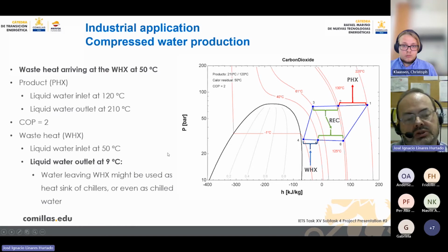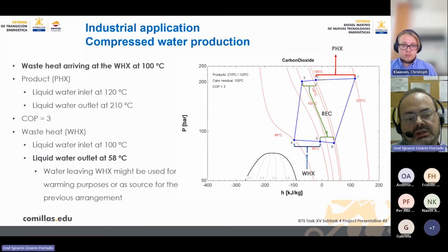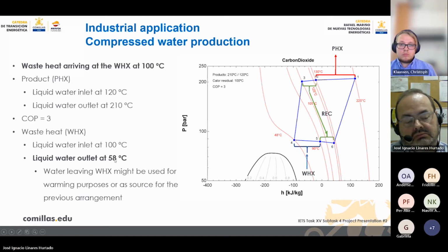Okay, this is with a low temperature source, and this is with a high temperature source of 100 Celsius degree. In this case, this has been moved up because we have a higher temperature. In this case, from 100 to 58 Celsius degree. This is 58, this is not 9, so in this case, perhaps we can use this temperature in order to warm up other streams in the factory, but in any case, we have achieved this product. In this case, because we have a higher temperature level in the source, we obtain a higher COP of 3, okay? But the performance is qualitatively the same.